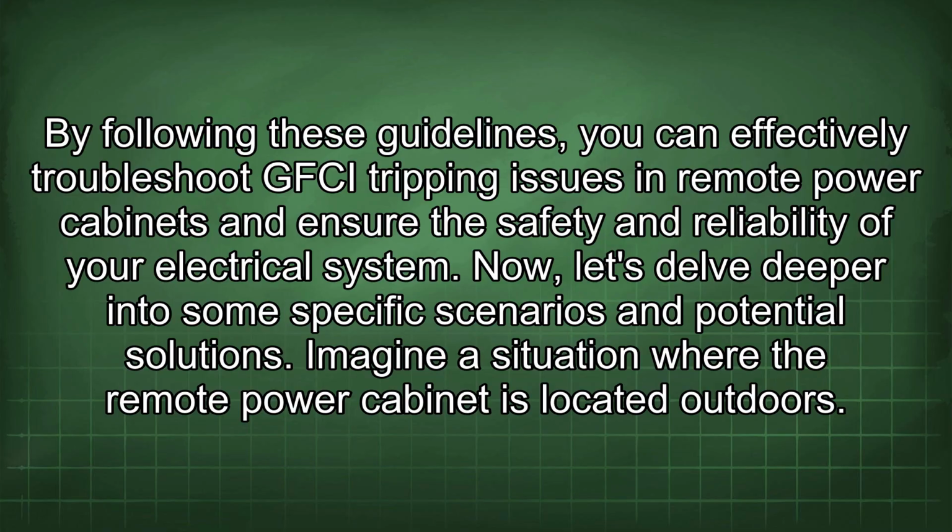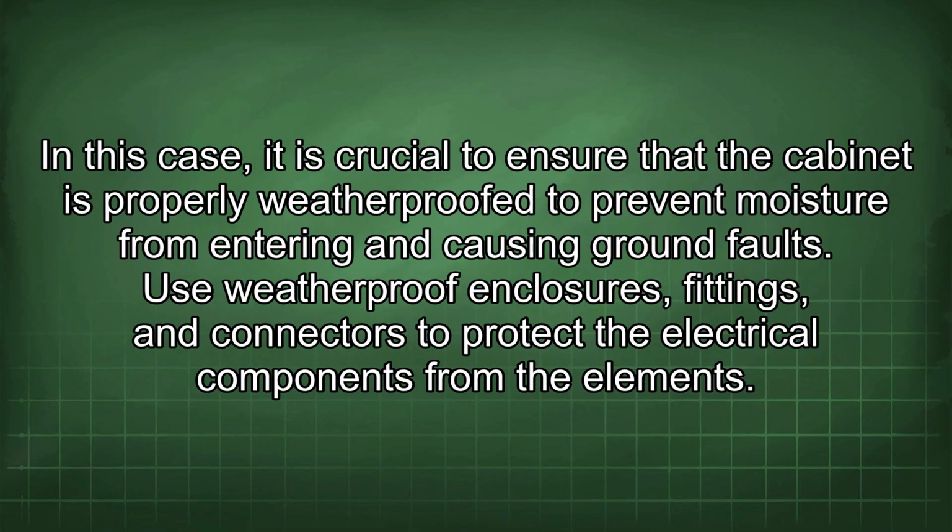Imagine a situation where the remote power cabinet is located outdoors. In this case, it is crucial to ensure that the cabinet is properly weatherproof to prevent moisture from entering and causing ground faults. Use weatherproof enclosures, fittings, and connectors to protect the electrical components from the elements.